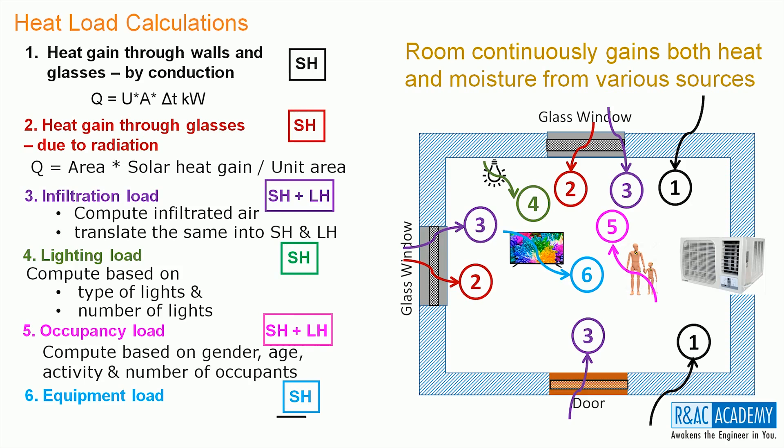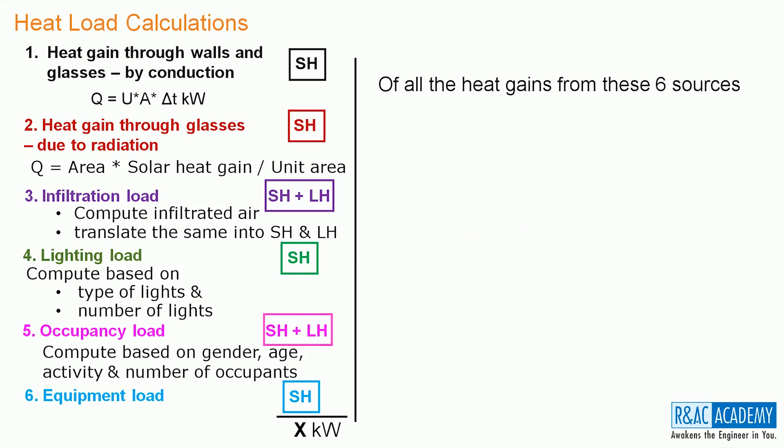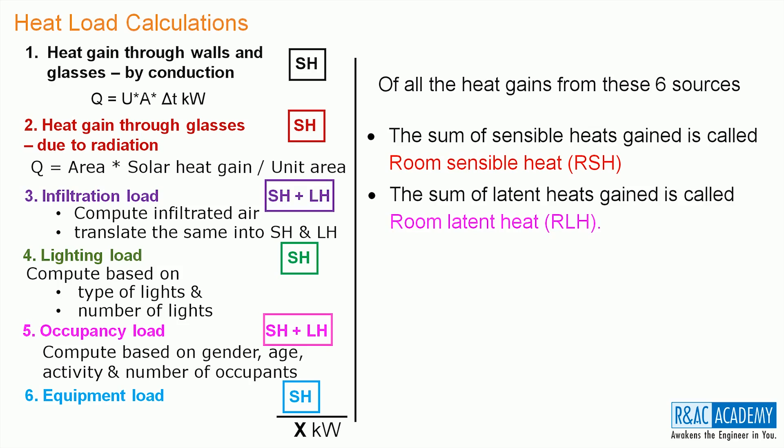Let us sum up the heat gains from these six sources and let that be x kW. Of all the heat gains from these six sources, the sum of sensible heats gained is called room sensible heat and the sum of the latent heats gained is called room latent heat. Finally, the sum of the RSH and RLH is called room total heat. Therefore, RTH equals x kW.